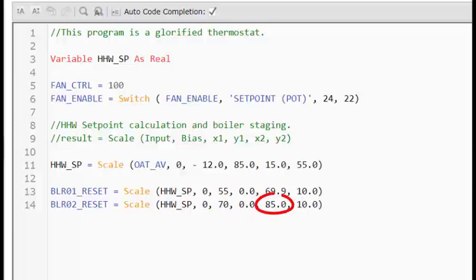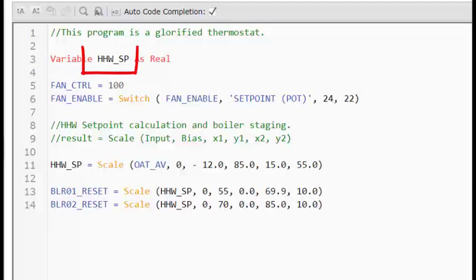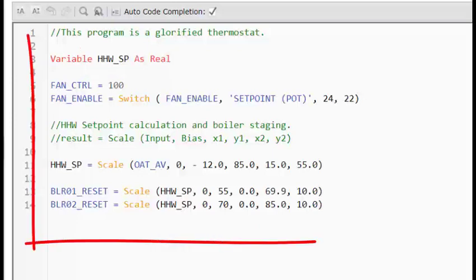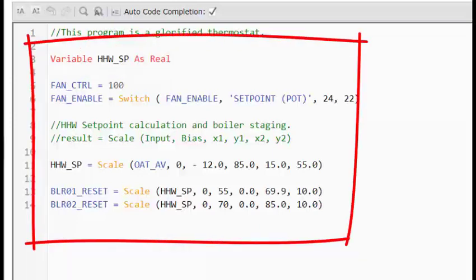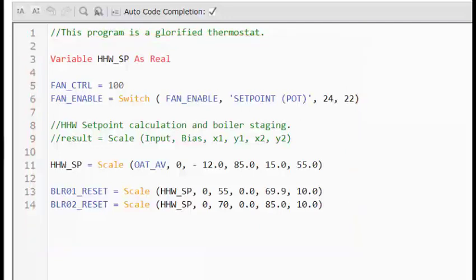What we have done here is declared a local variable. This box of information containing the heating hot water set point is only available in this program and cannot be accessed by another program, even on the same controller. It also means that the information contained in this variable cannot be accessed or displayed on the graphics. So this could be an advantage or a disadvantage.